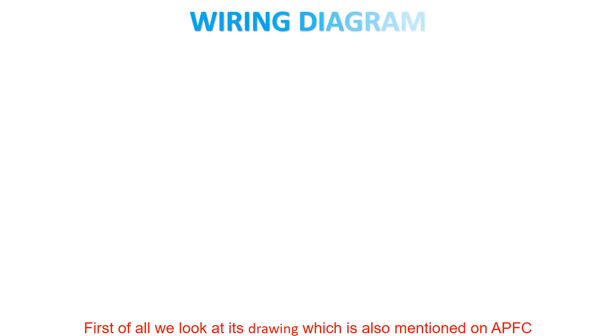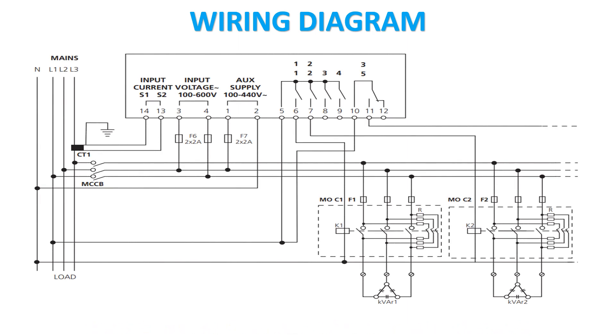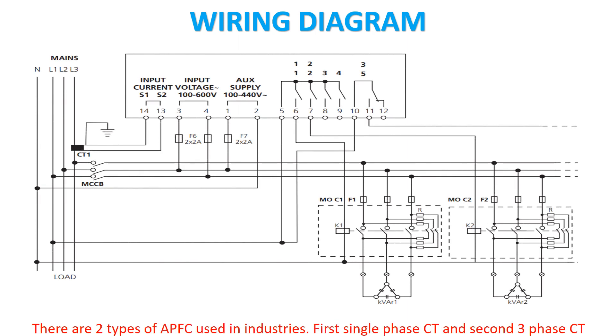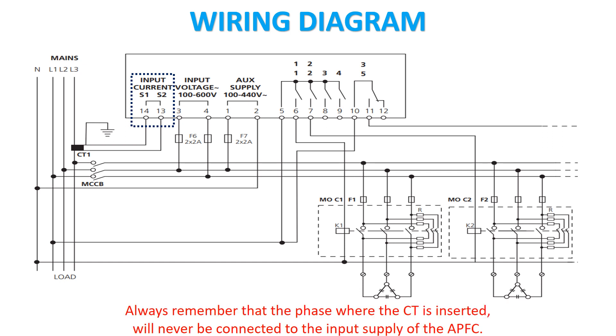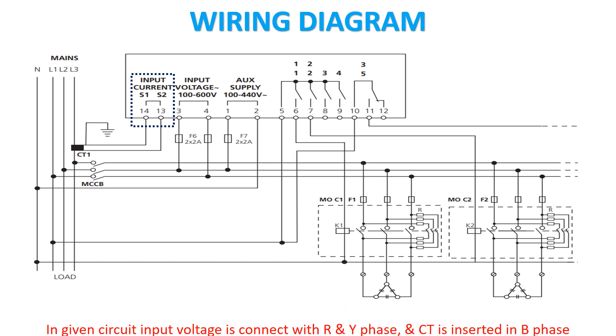First of all we look at its drawing, which is also mentioned on APFC. There are two types of APFC used in industries: first single phase CT, and second three phase CT. This model operates on single phase CT. Always remember that the phase where the CT is inserted will never be connected to the input supply of the APFC. In the given circuit, input voltage is connected with R and Y phase, and CT is inserted in B phase.